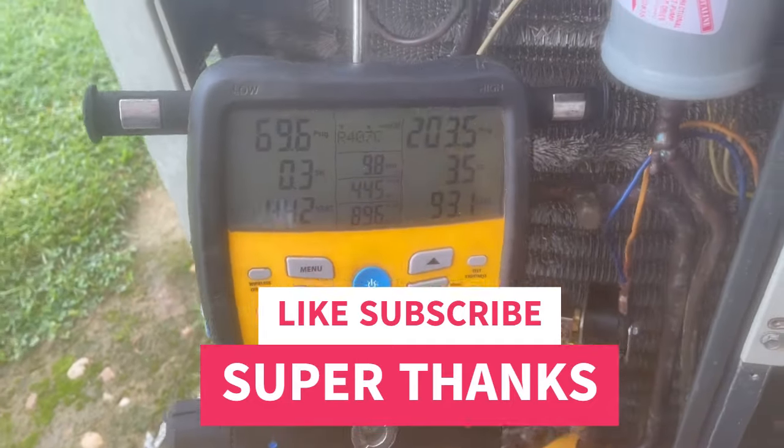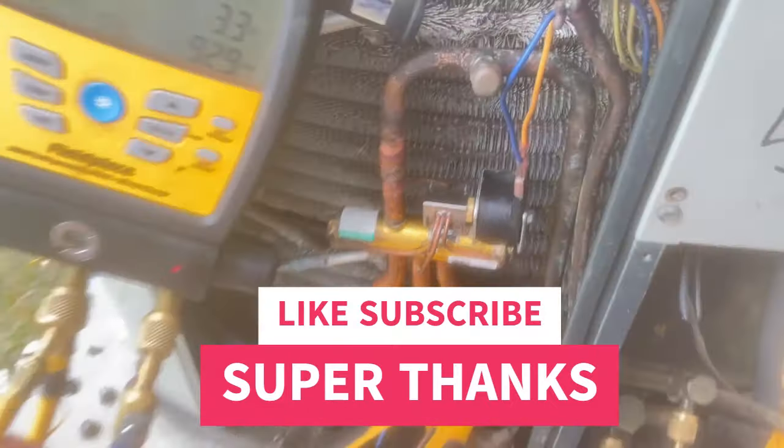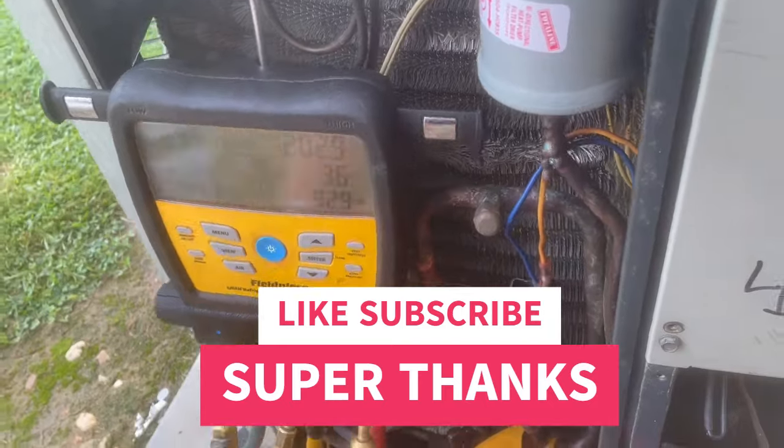Well, all right, guys, the reversing valve fixed the problem. We've got 407C back in it. Our compressor is good.